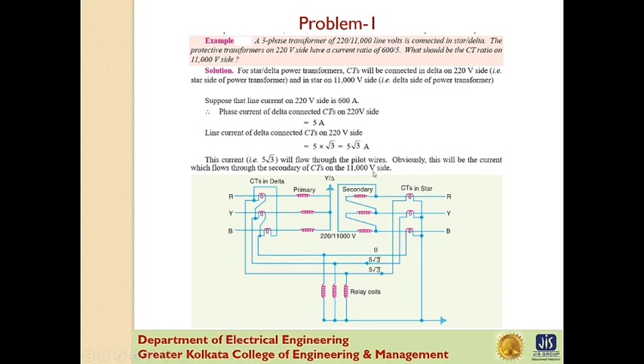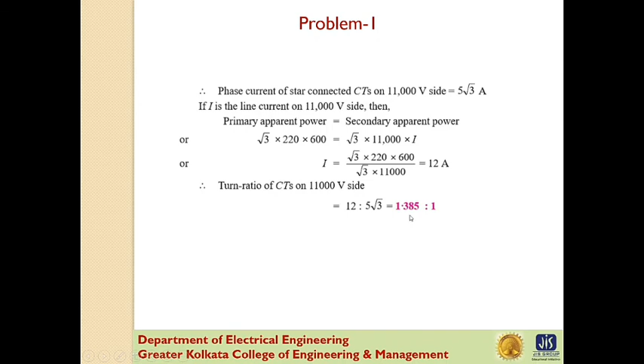Now the primary apparent power is equal to the secondary apparent power. Now it is assumed that I is the line current on the 11,000 side. So what is the relation? What is the formula of power? Root 3 VI. V is 220, I is 600, and here we assume I is the line current and the voltage is given 11,000. So by solving this equation, we get I equals 12 ampere. Now this is the primary current of the CTs on the 11,000 volt side. So the turn ratio of the CTs on the 11,000 volt side is 12 is to 5 root 3, which is equal to 1.385 is to 1.